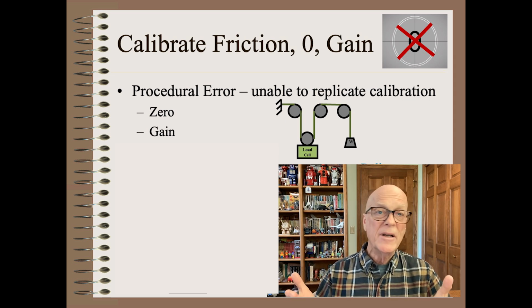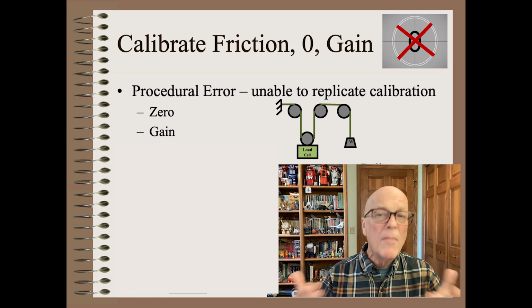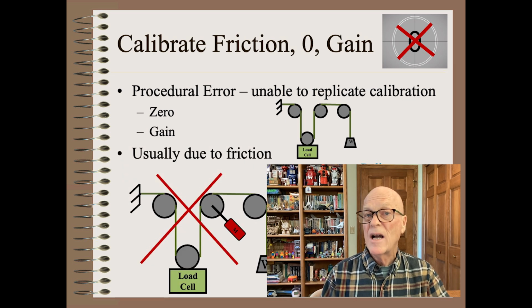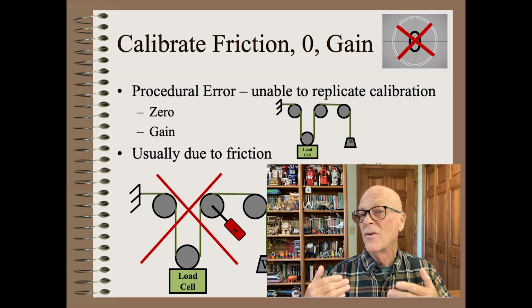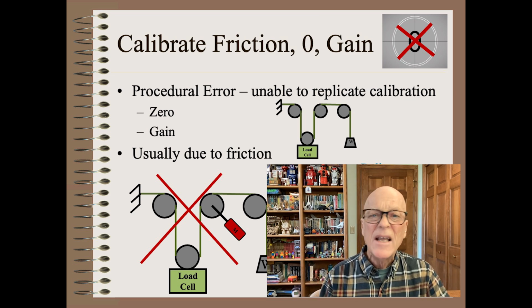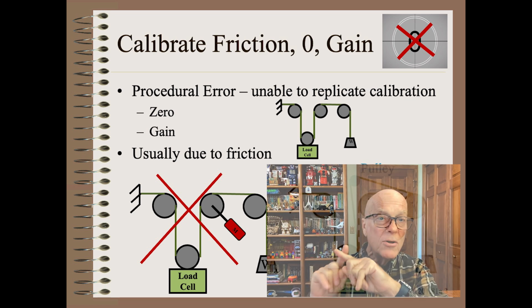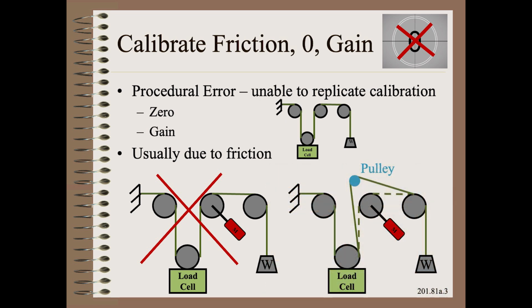The most common is for the test to have too much friction. The most common way here is that the strap is routed over a high friction element, such as a motor-driven roller. This is a no-no. You must add a pulley to just barely clear the high friction element to take it out of the calibration procedure.